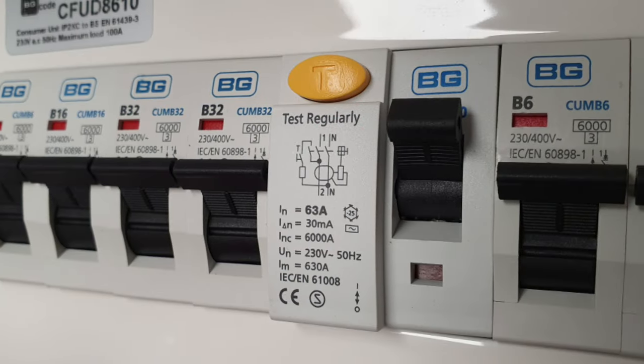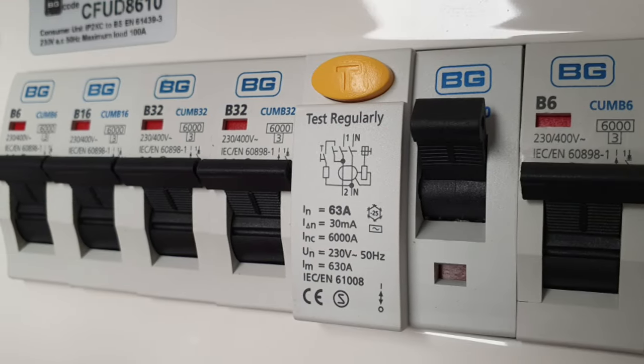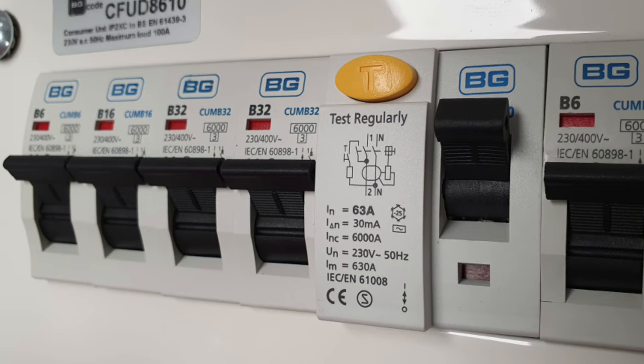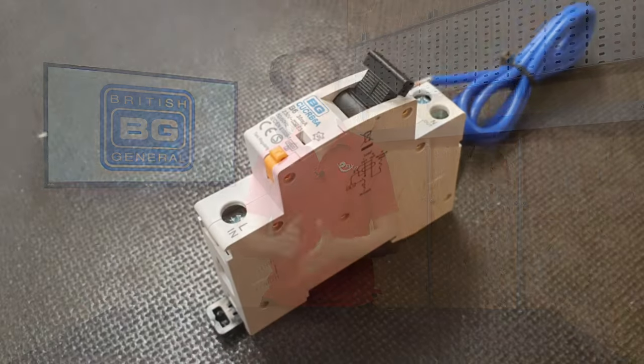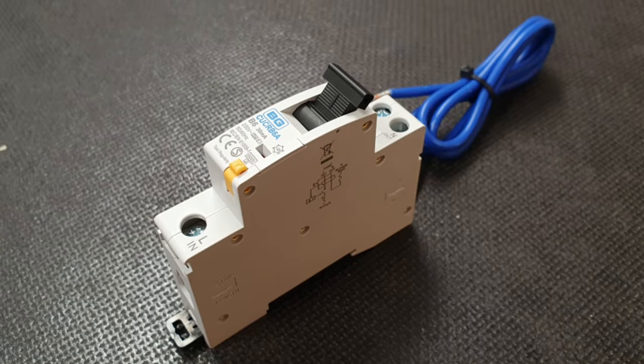So to summarise, an RCCB is most likely to conform to BS EN 61008 and will protect against earth faults, such as when a line and CPC come into contact with each other or someone gets a shock to earth. It has no overcurrent protection, which is why you usually see them as the RCD protection in a split load board used in conjunction with MCBs to give the overcurrent protection. An RCBO is most likely to conform with BS EN 61009 and offers protection against earth faults, shocks to earth, overload, and short circuit protection. So there we go. That is the fundamental difference between an RCCB and an RCBO explained.